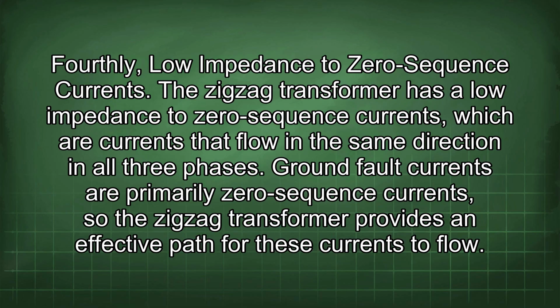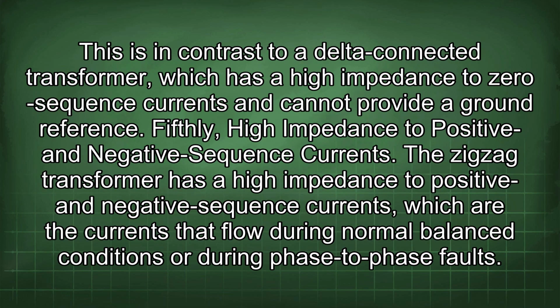Fourthly, low impedance to zero sequence currents. The zigzag transformer has a low impedance to zero sequence currents, which are currents that flow in the same direction in all three phases. Ground fault currents are primarily zero sequence currents, so the zigzag transformer provides an effective path for these currents to flow. This is in contrast to a delta-connected transformer, which has a high impedance to zero sequence currents and cannot provide a ground reference. Fifthly, high impedance to positive and negative sequence currents.